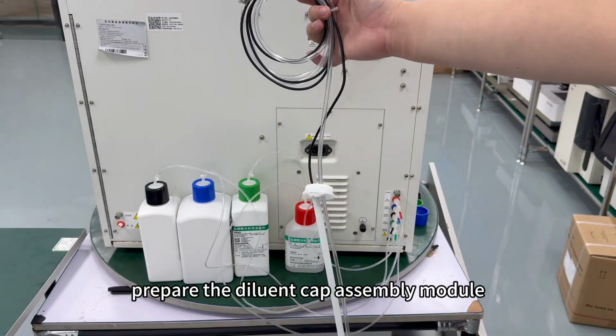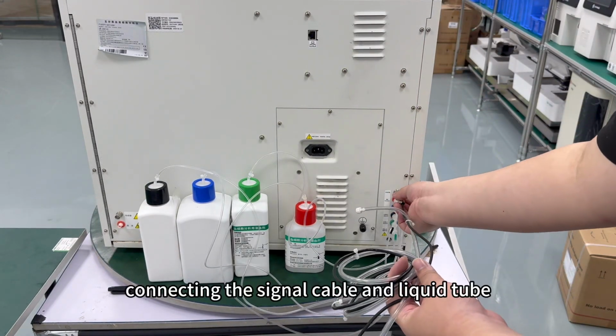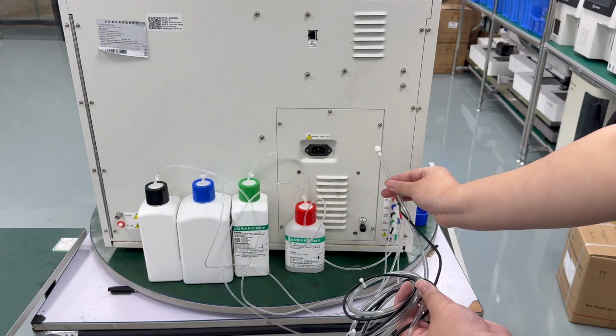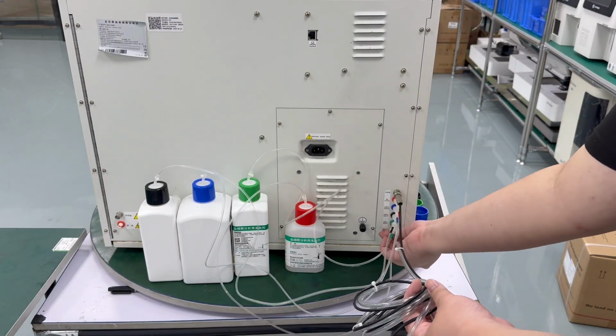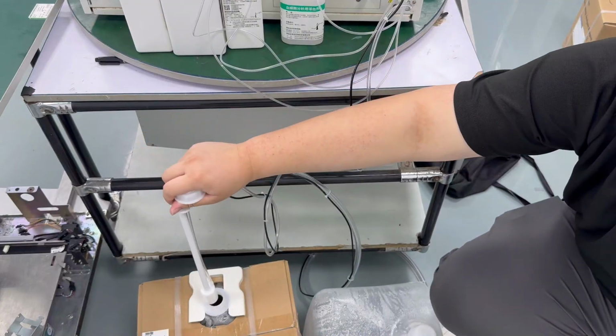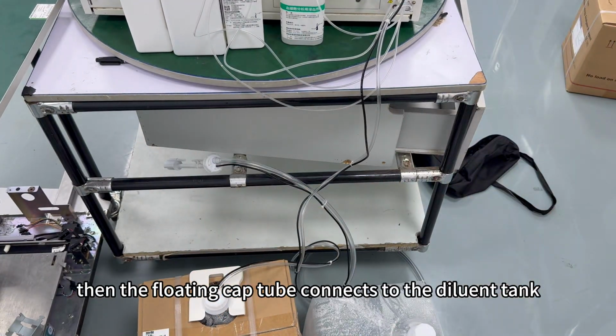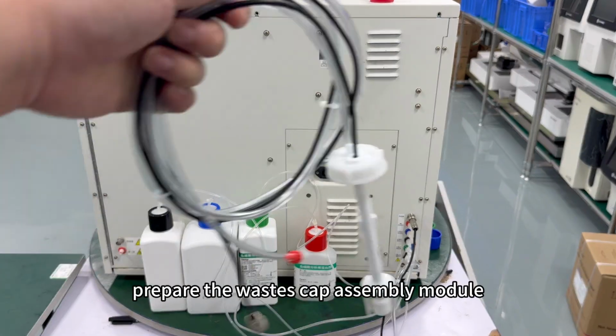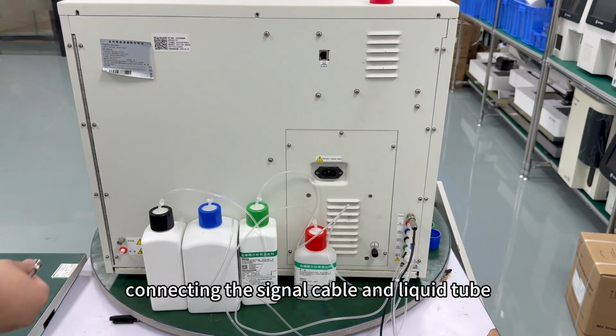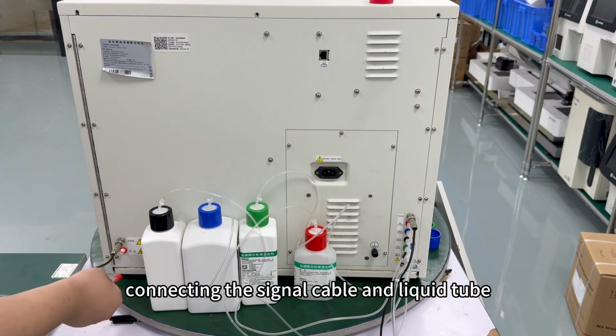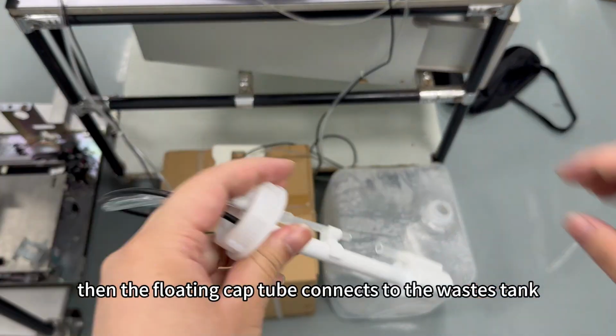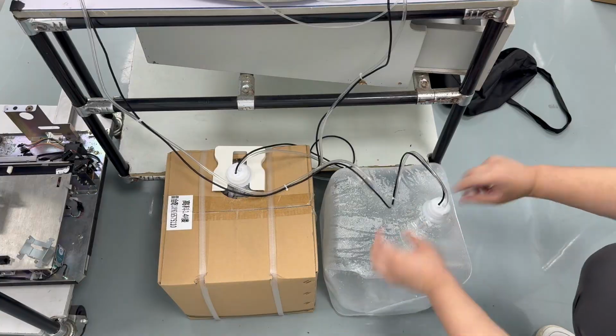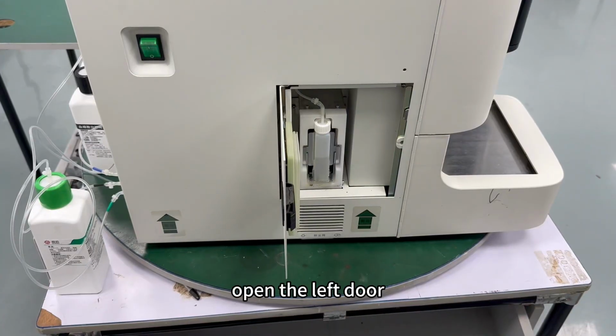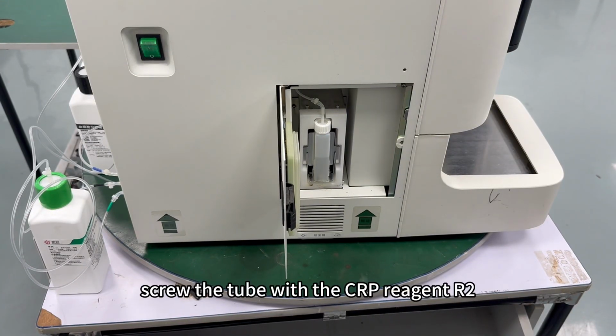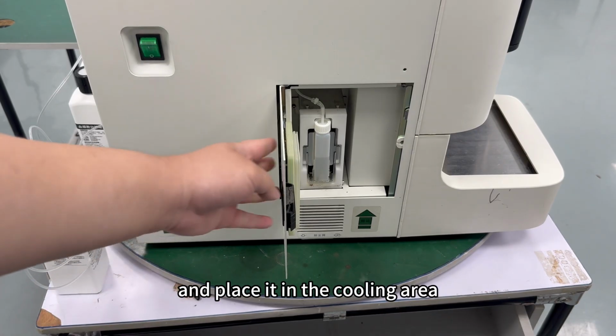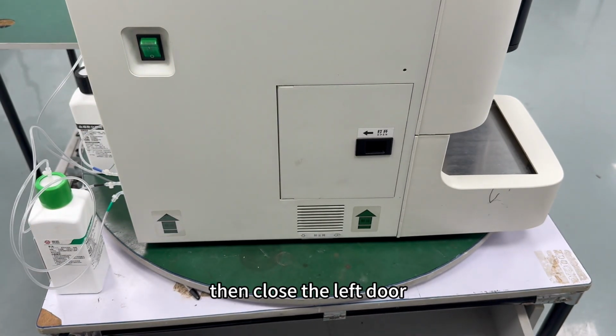Prepare the diluent cap assembly module. Connect the signal cable and liquid tube. Then connect the floating cap tube to the diluent tank. Prepare the waste cap assembly module. Connect the signal cable and liquid tube. Then connect the floating cap tube to the waste tank. Open the left door. Screw the tube onto the CRP reagent R2 and place it in the cooling area. Then close the left door.